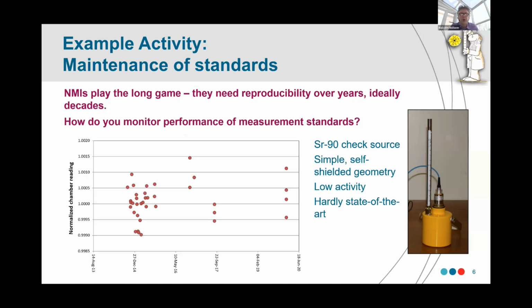So this is data from our lab. And over 6 years, you see just using this, you can monitor the performance of an ionization chamber to better than 0.1%. So sources are very good for providing that reference source of radiation to monitor the performance of our detectors.